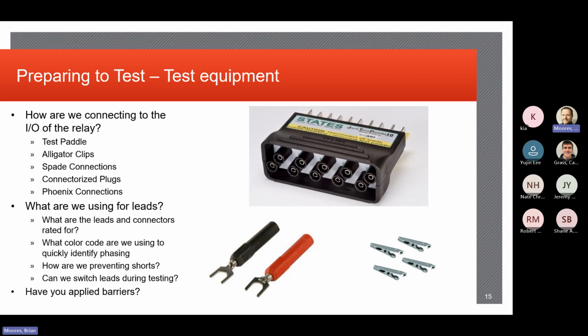Again, I've had folks run, I've seen folks applying current from a test set and letting it run, and it was 10 amps of current, but the lead was only rated, or the probe was only rated for 6 amps. So guess what happens? The probe melted, right? So it's paying attention to the ratings of your equipment.